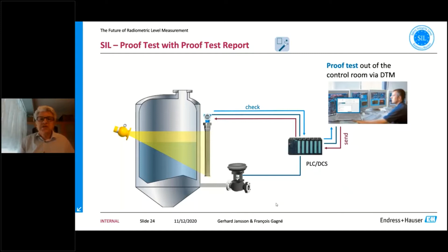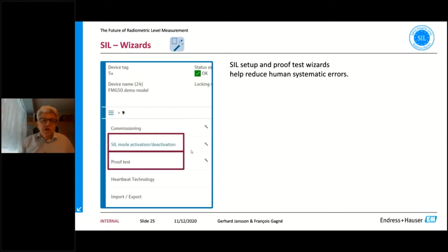In that regard, we use Device Care, which is a free software from Endress+Hauser. In principle, there is a wizard there, referred to as the SIL wizard, that will step you through the whole process to do this SIL configuration, activation, and the proof test. So what you do here, first of all, you need to unlock it. If it's already in SIL mode, it's locked, so no one can go in and tamper with it. It will unlock, you can do the proof test, and then afterwards you lock it again, so no one can go in and tamper with it.